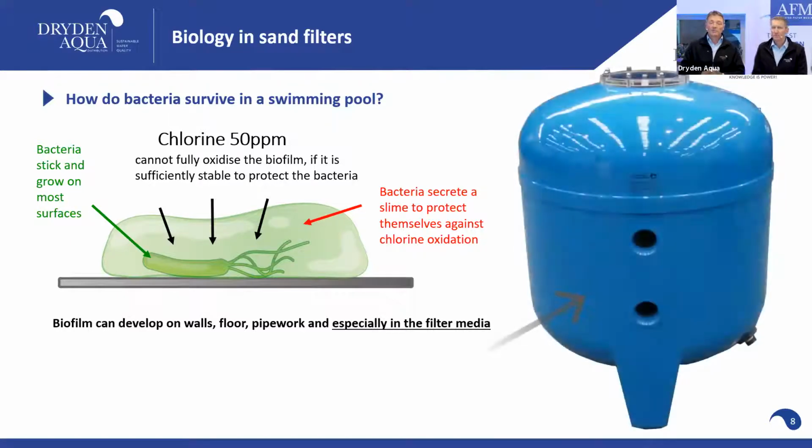Yep. And that's really it. It would be wrong to say this would not oxidize this biofilm. It will do this to a very big extent, but as you said, not 100%. Only 99.99. And the thicker this biofilm, the more resistant it becomes against chlorine oxidation. As the bacteria reproduce so quickly, they're also evolving and becoming chlorine resistant at the same time.